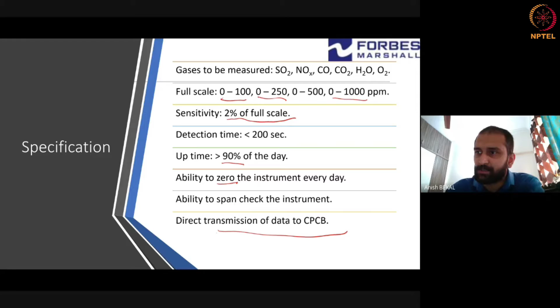And nowadays you should also be able to remotely zero. That means CPCB typically says that if I send a command from CPCB Delhi, for example, I should be able to do a zeroing on the instrument remotely, or a span check of the instrument, and all the data has to go to the Central Pollution Control Board directly without any interference in the middle. So when you say a sensor has to be built, it is now a summation of multiple technologies or multiple areas, starting from IoT to spectroscopy, to electronics, to mechanical systems. All these technologies have to come together to form one of these systems. So it is very important to understand the interconnections between them, the constraints offered by all of them, and then make the system work.